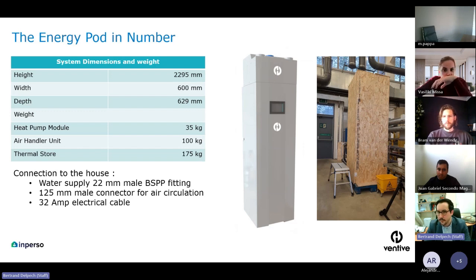The main point to account for during the installation is the connection of the water supply of the house to the Energypod. It's really important that this 22 millimeter male BSPP fitting or an adapter is supplied on site. We had an experience where we installed an Energypod on site and the installer didn't know what the sizing was. It was back in France, and in France it's not something that you can supply quite easily. It needs to be ordered, so that delays the installation process by about 2 days. So it's something that needs to be accounted for when the installation planning is done.